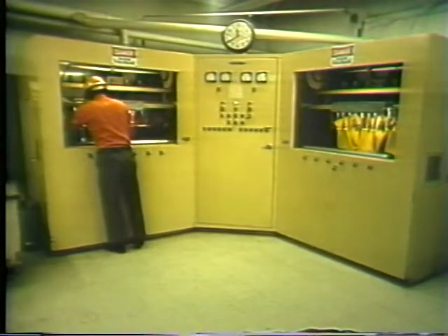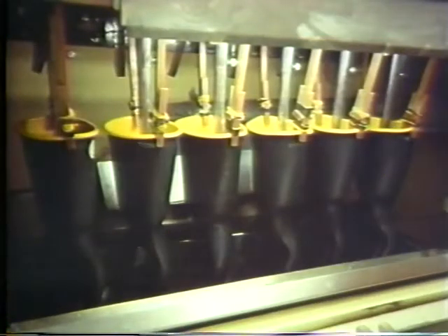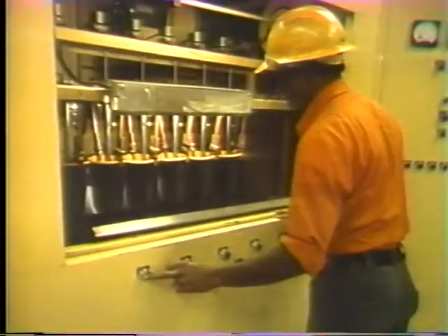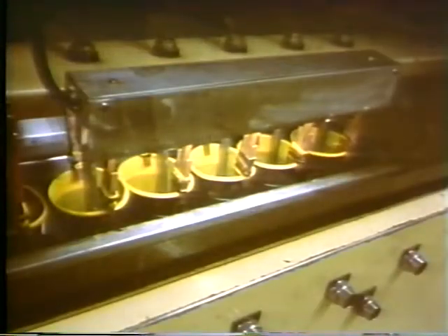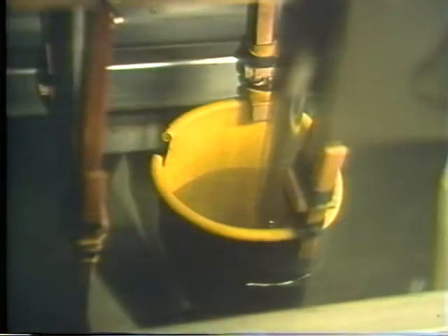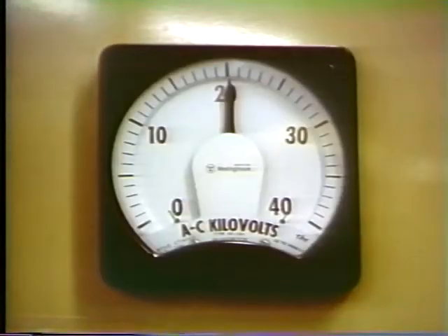Here's a typical test rig for rubber gloves and sleeves. Gloves are hung in line on a rack and filled with water. Then the rack and the gloves are lowered into a tank that's also full of water. While the gloves are submerged, 20,000 volts are applied across the material. If the gloves are good, the voltage will hold.